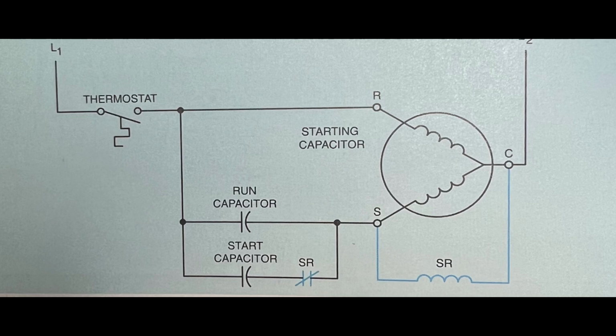When the power is connected to the motor, both the run and start windings are energized. At this time, both the run and start capacitors are connected in the start winding circuit. The rotating magnetic field of the stator induces a turn in the rotor of the motor. As the rotor begins to turn, its magnetic field induces a voltage into the start winding, increasing the total voltage across the winding. Since the coil of the potential relay is connected in parallel with the start windings, this voltage increase is applied to it also, causing the normally closed contact connected in series with the starting capacitor to open and disconnect the starting capacitor from the circuit.